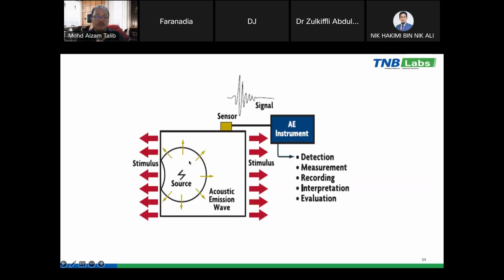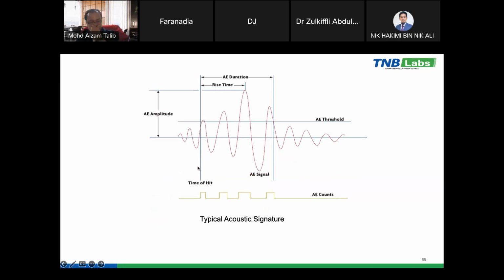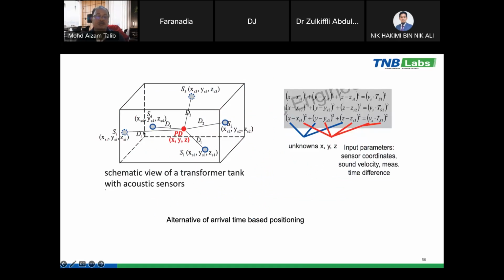Here we put a sensor. When there is a PD occurring in the transformer, it will generate this acoustic emission wave. And then when we have different sensors, based on the calculation of the arrival time of each signal coming to the sensors, we are able to pinpoint the location of the faults. So this is the typical acoustic signature. We analyze it in terms of its amplitude, rise time, duration, energy, and so on. So here we put different sensors. We have a PD, and based on the arrival time of each signal reaching the sensors, we are able to pinpoint the locations.